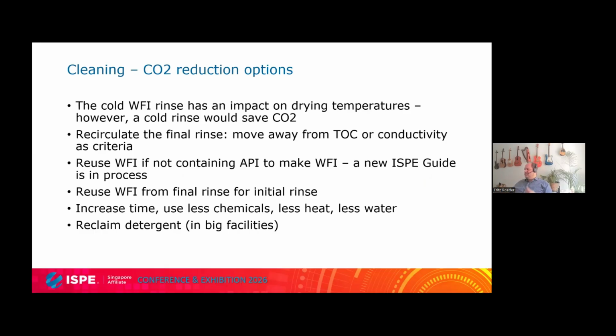So my options for you: first, you can recirculate this. Bring the 200 liters down to maybe 30 or 50 liters and let them recirculate. But for that, it's necessary to move away from TOC or conductivity as criteria for cleaning validation. Many people rinse until they reach the same conductivity the water had before, but then you lose a lot of water. What we've done is step away from TOC and conductivity criteria and instead use time or flow as criteria, then recirculate. If you recirculate the water, you won't get down to the conductivity you need - you can't meet that spec anymore, but you don't need to. It's okay to use other criteria, and then you can save 90% of the final rinse.